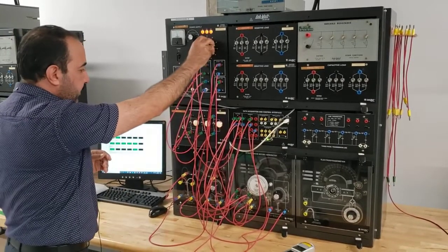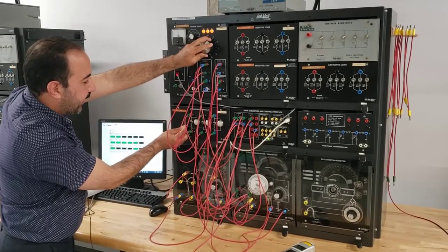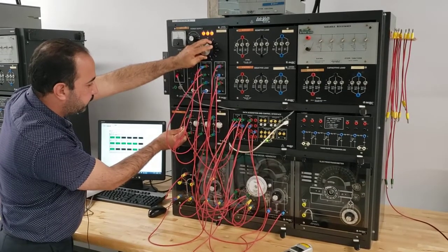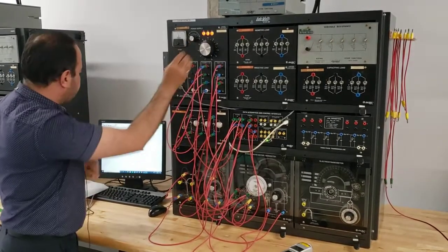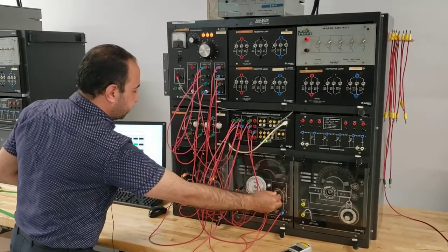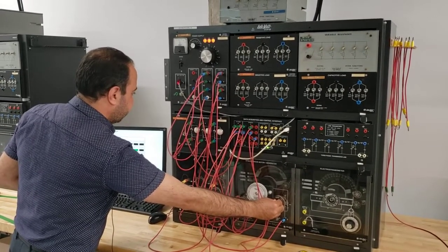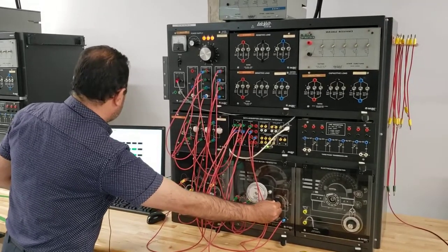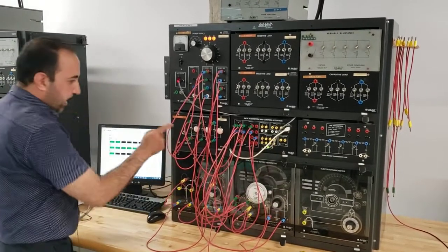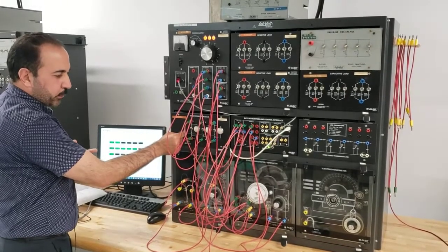But if I try to connect them while they are shining, when there is a little difference between the voltage or the frequency for both of them, let me make a little change for this and try to connect them while the lamps are shining, they are not off. Here, there is a noise. I don't know if you hear that or not.